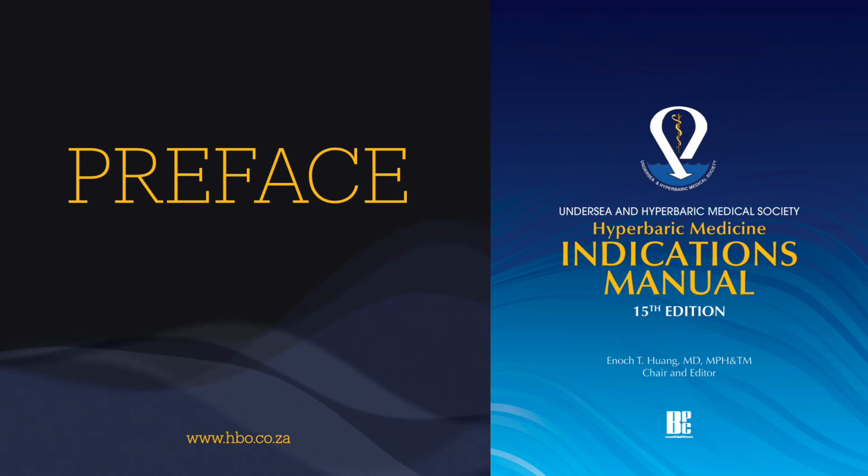Right. And the manual also lists common equivalent units you might see: 33 feet of seawater, 14.7 pounds per square inch, PSI, 1 atmosphere absolute, 1 ATA, 1.013 bars, and 101.325 kilopascals. It clarifies that gauge pressure usually measures pressure above atmospheric, while absolute pressure includes atmospheric pressure. Understanding those units and the concept of pressure relative to sea level is pretty foundational for dosing therapy accurately.